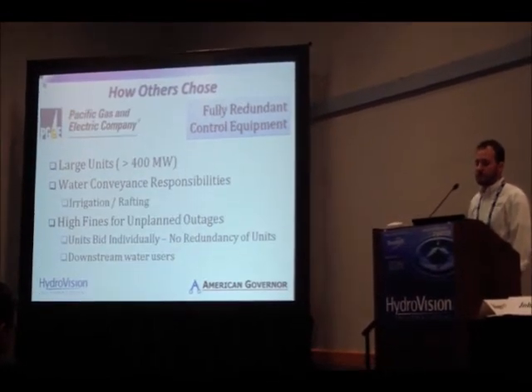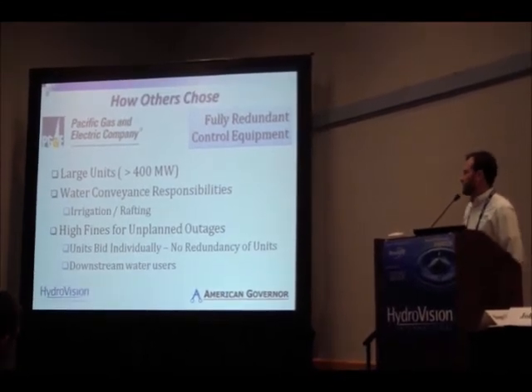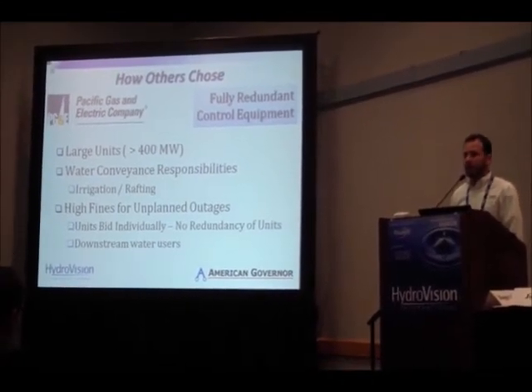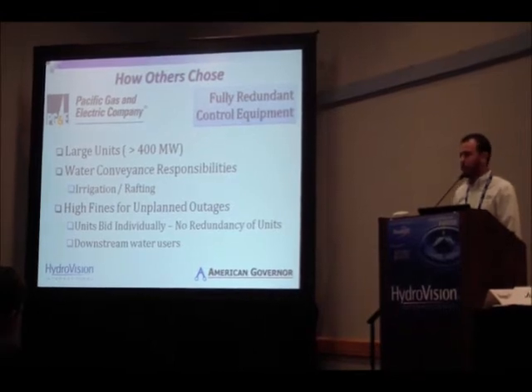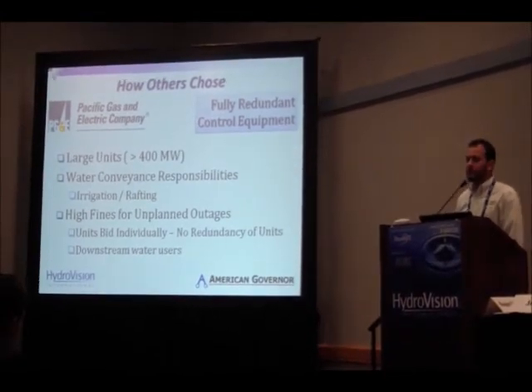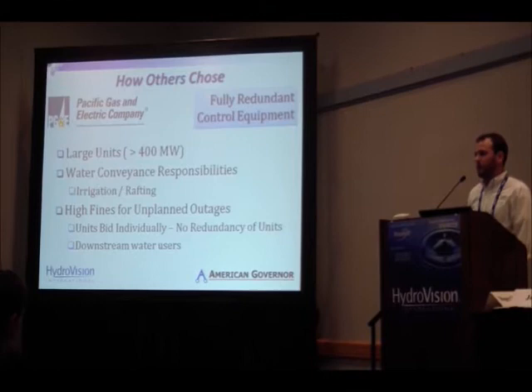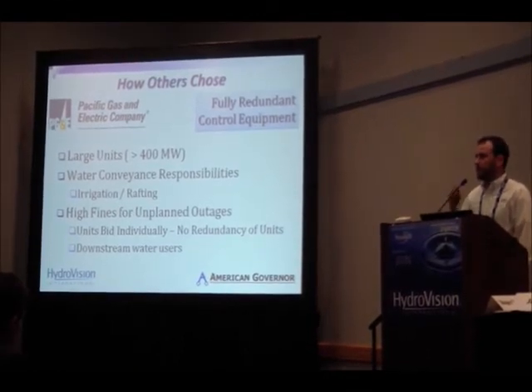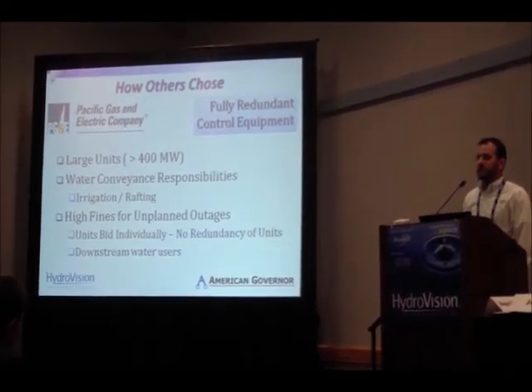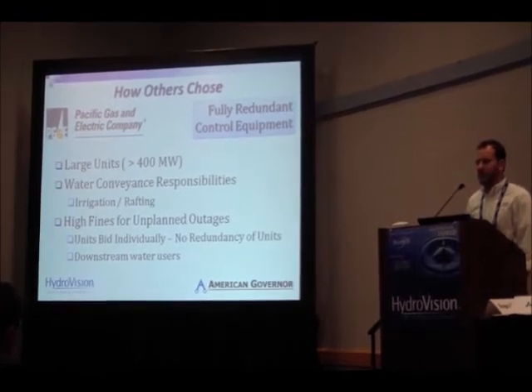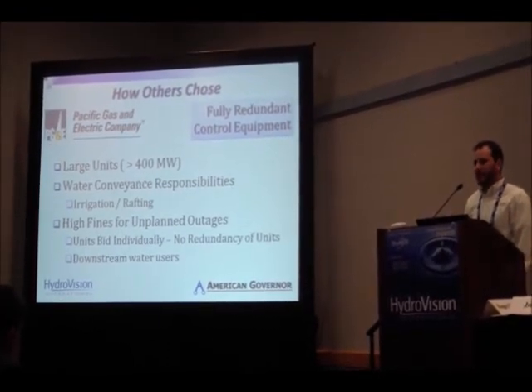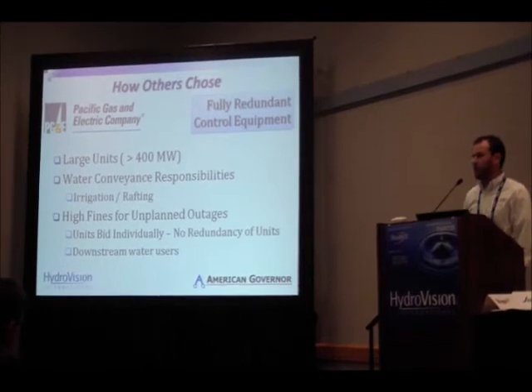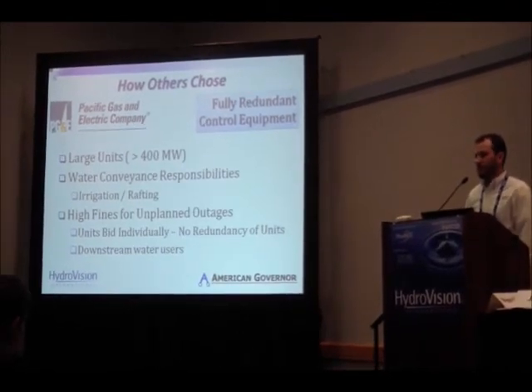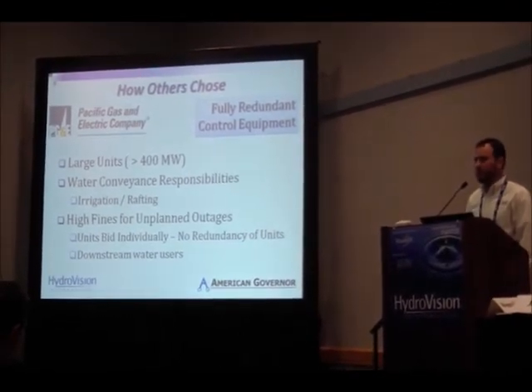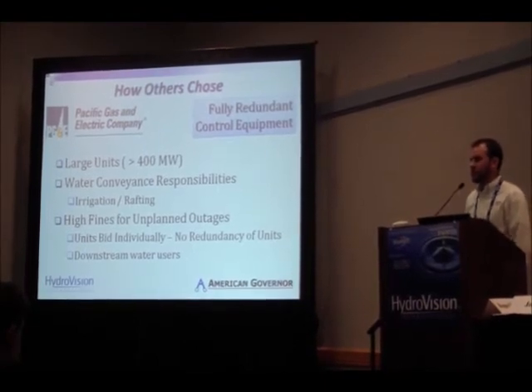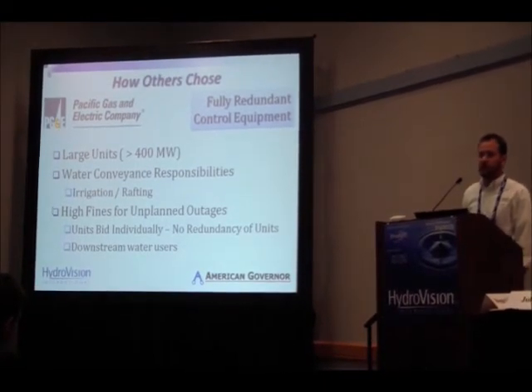Now the final situation, Pacific Gas and Electric in California has a lot of large units, well, a few large units, over 400 megawatts. They also have a lot of water conveyance responsibilities. These are the guys who are California, the valley, irrigation, recreation. If they can prevent a single forced outage that results in a loss of flow, that might cost them $100,000, $200,000. If they can prevent a single event by going with a redundant system, it pays for itself. These are the situations where redundancy really comes into play.